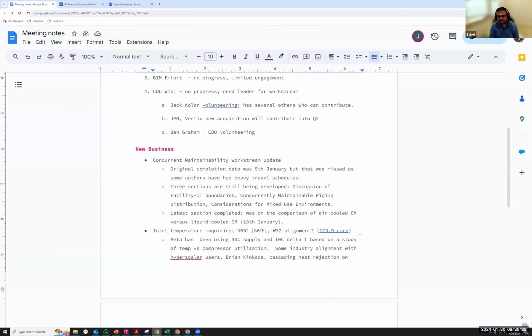Right, so again there are different ways on how you can do it, and it depends on how the system is set up. What we're looking into is trying to optimize the maximum delta T across the chiller so the chillers can be utilized efficiently. In that case, we're mainly modulating the flow on the primary side rather than mixing, because in case of low load, that might just dilute the delta T. So again, it depends on how the system is set up.